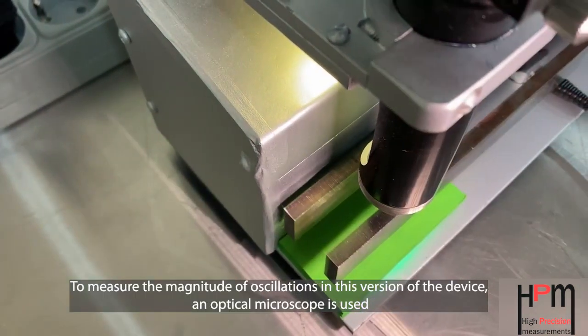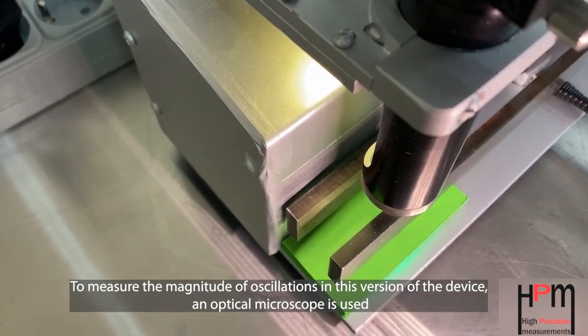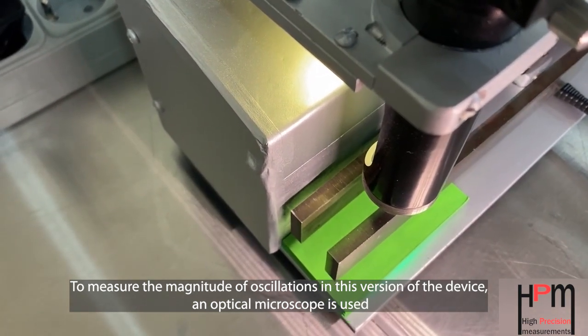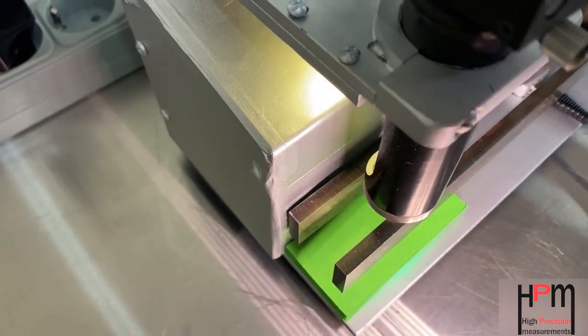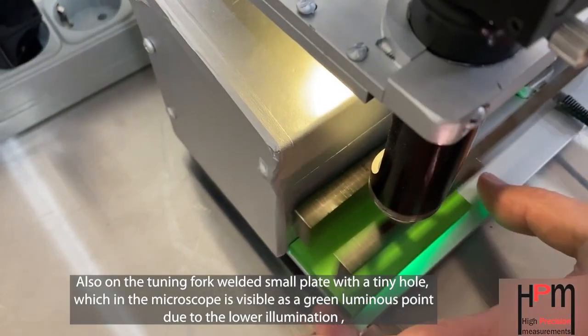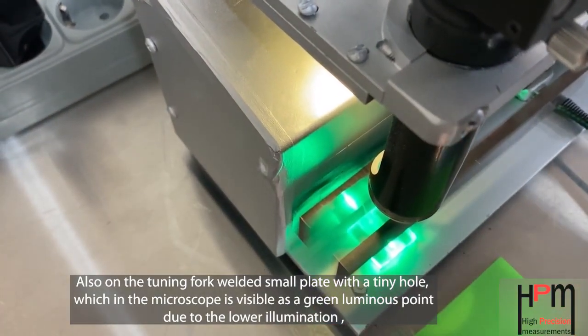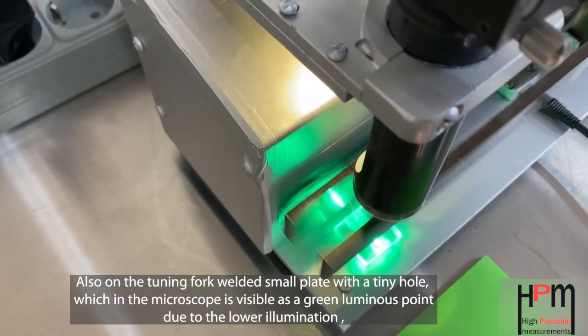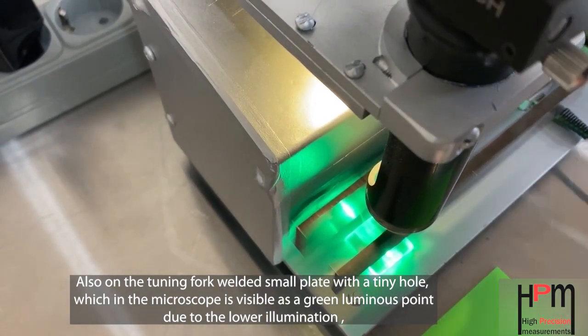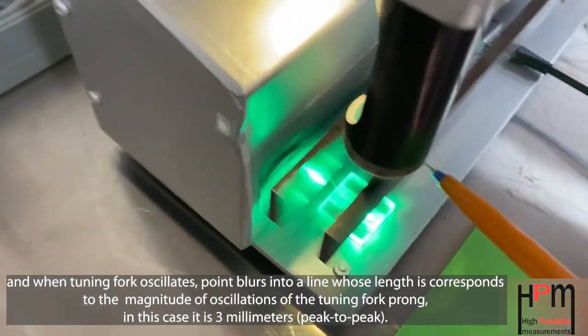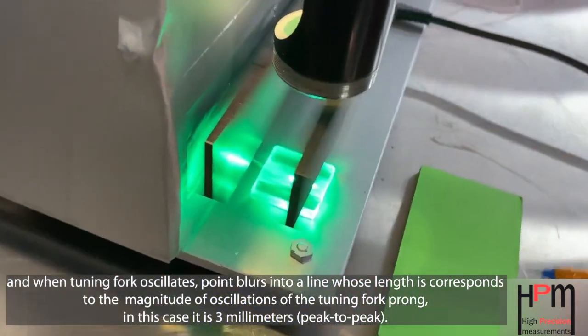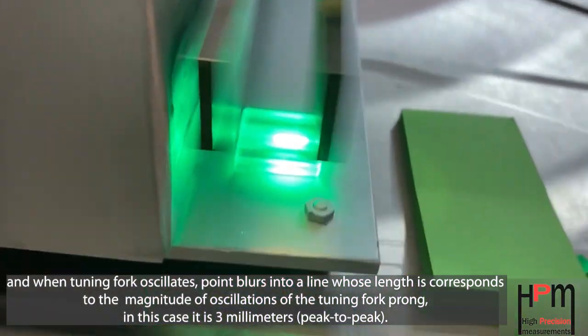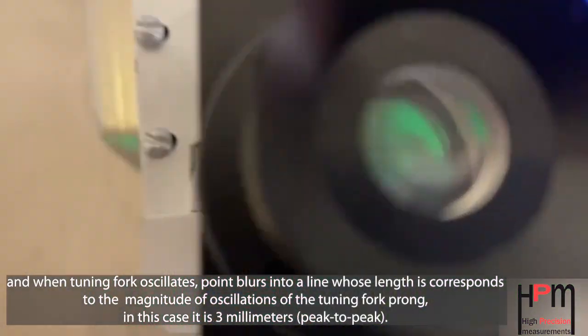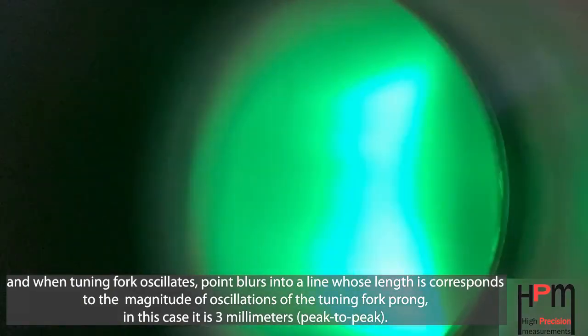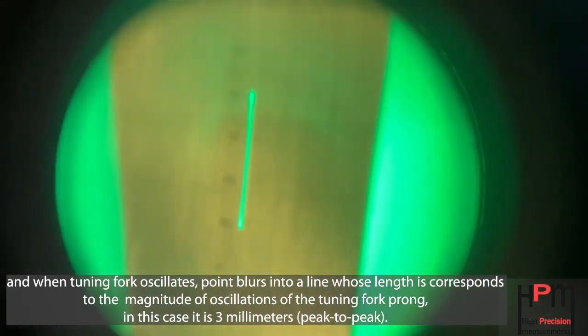To measure the magnitude of oscillations in this version of the device, an optical microscope is used. Also on the tuning fork, a small plate with a tiny hole is welded, which in the microscope is visible as a green luminous point due to the lower illumination, and when the tuning fork oscillates, the point blurs into a line whose length corresponds to the magnitude of oscillations of the tuning fork prong. In this case, it is 3 millimeters. Peak to peak.